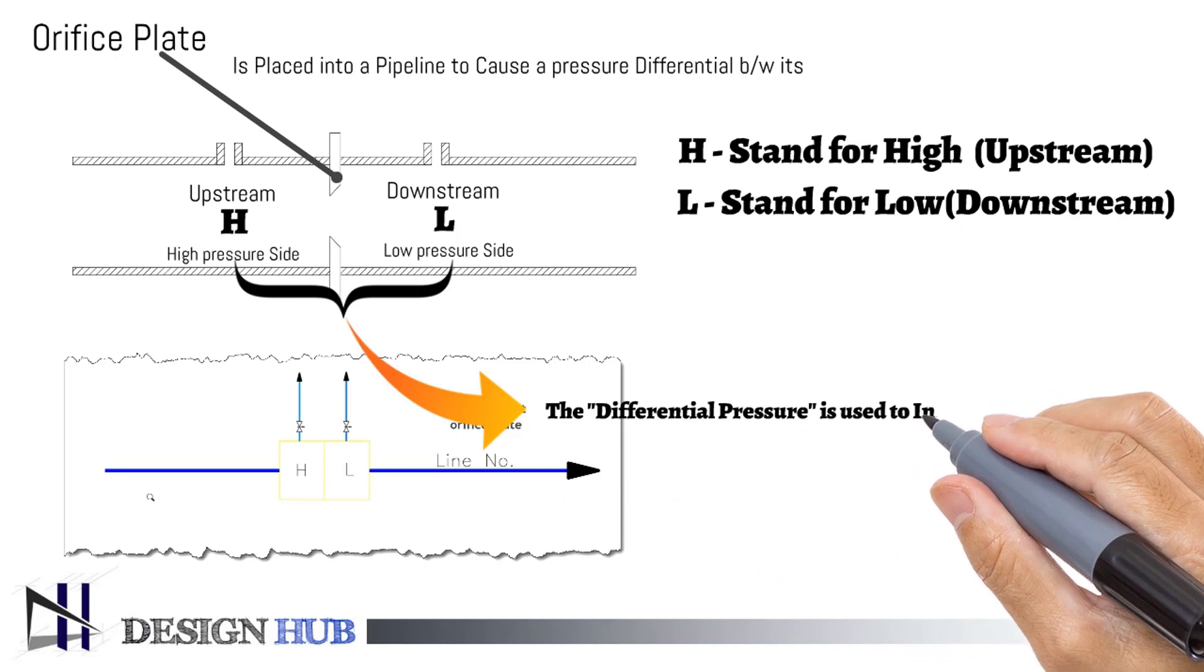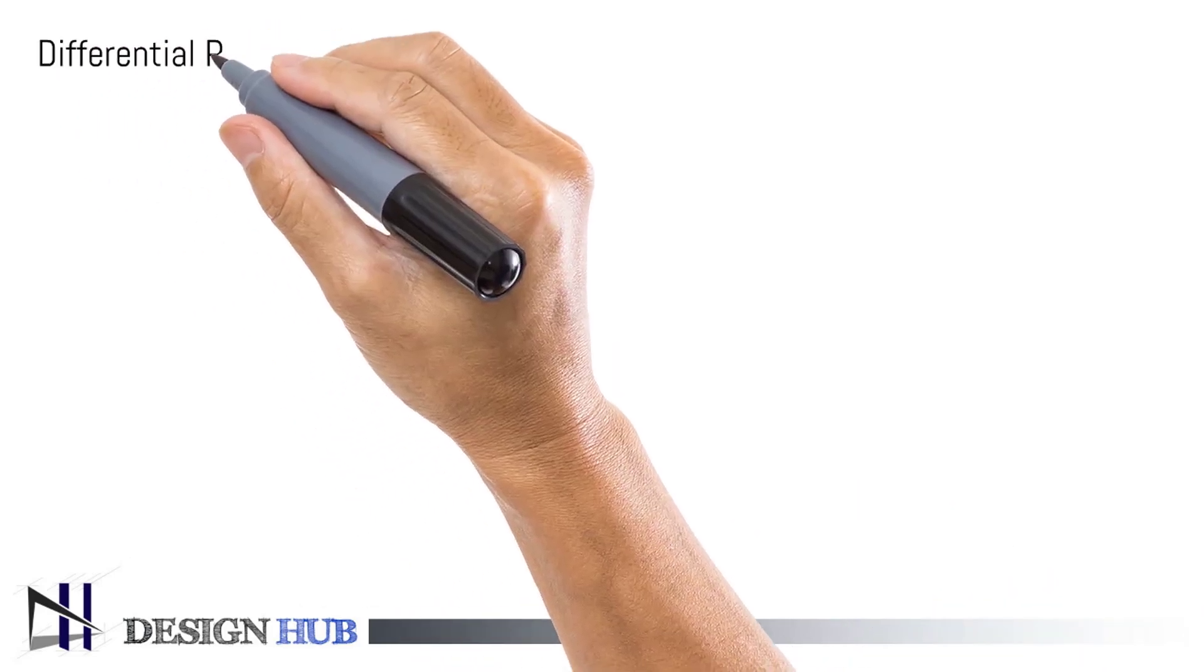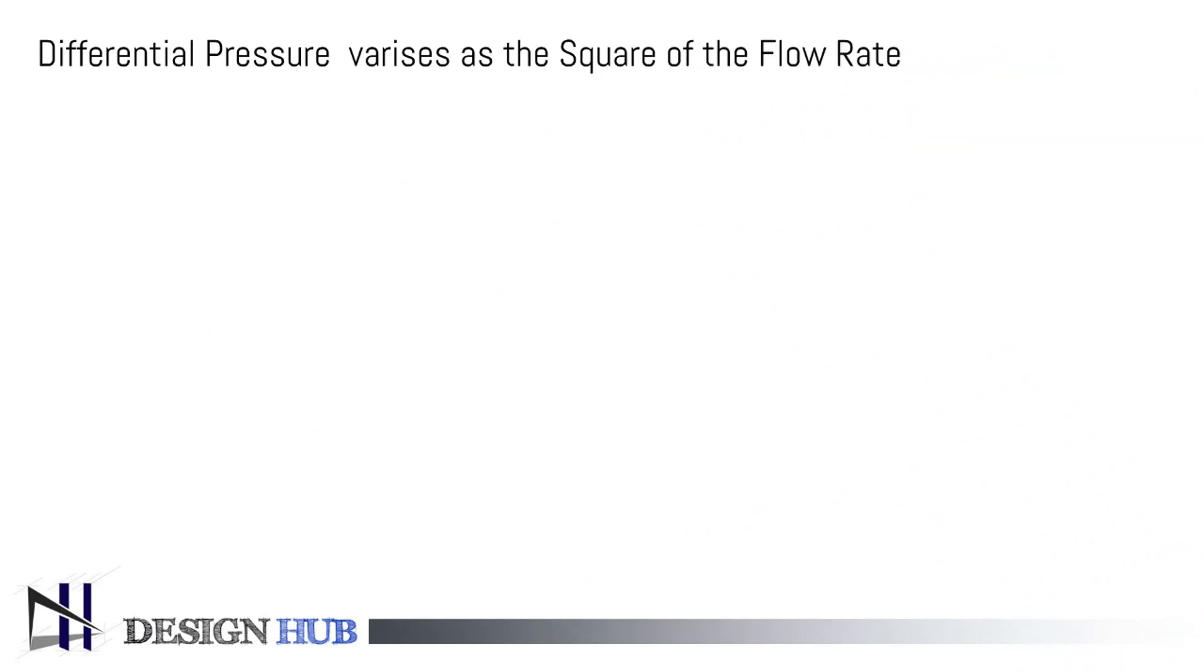The difference between upstream and downstream pressure is used to indicate the flow rate. Differential pressure varies as the square of the flow rate. You can see this in the formula and chart.